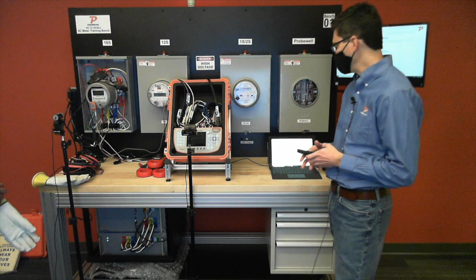You make it hot. Give me a 4-wire Y. That's what we're dealing with here, right? So what's the difference between a 4-wire Y and a delta? We just spoke about that. The difference is in voltage. We could take our voltmeter and measure to verify that.